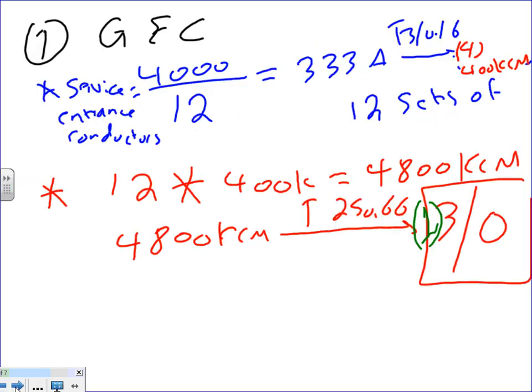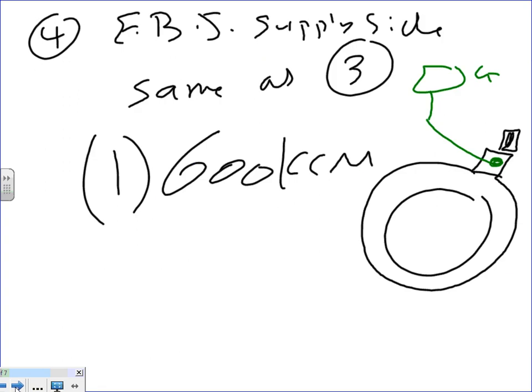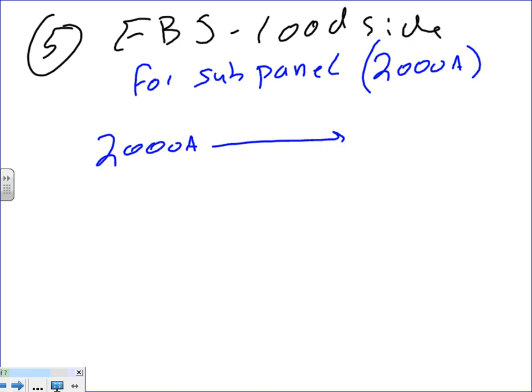Okay, so I'm going to size it, guys, directly based on, if you read through what we're saying for number 5, it says table 250.122, based on the overcurrent device. So what's the overcurrent device here? 2,000 amp. Take this one to table 250.122, and you'll have 250 kcm. How many?